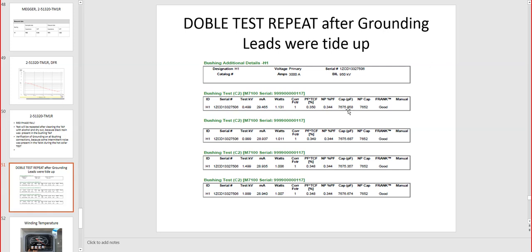Doble test repeat. After repeating the Doble test, we actually found out that the results are fine. So we can see here that the actual C2 is very, very close to the manufacturer. So we did the test again at 500, 1000, 1500 and 2000 volts. So the results you can see here are very similar. So you have the nameplate data and then the reading data, capacitors in picofarads, and then the actual capacitance reading.